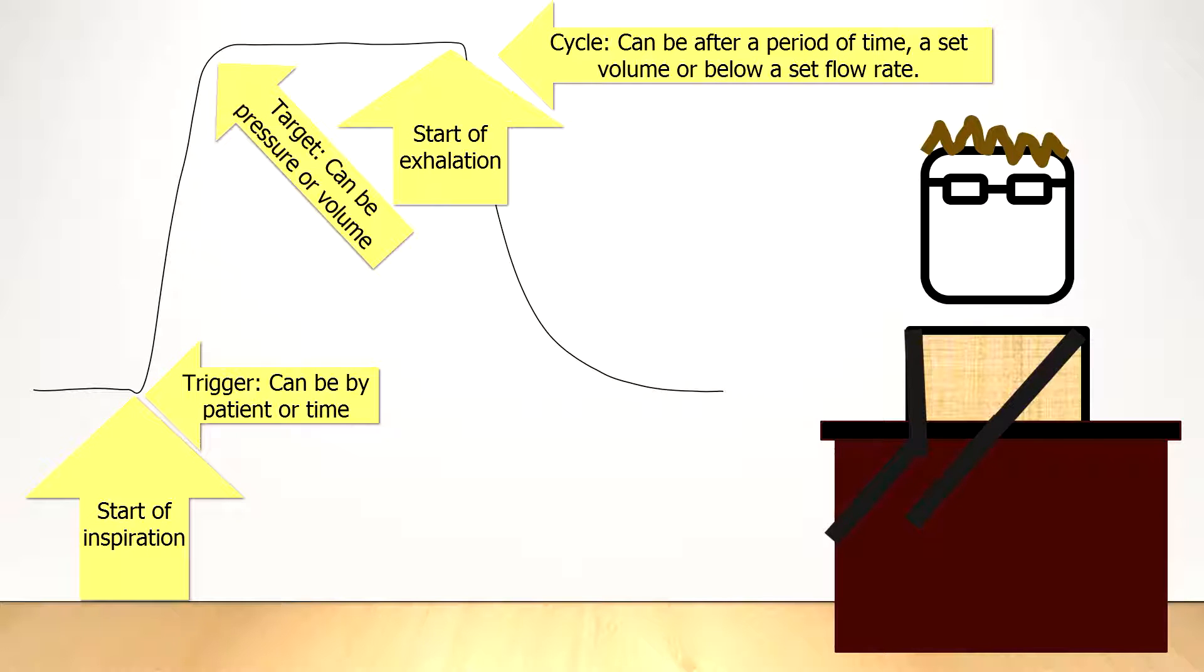If the patient is on a pressure support ventilation, which we'll discuss more about in a future talk, the ventilator will cycle once the flow rate is below 25% of the initial flow, as it is a marker to the ventilator when the patient has spontaneously stopped inhaling and wishes to start exhalation.